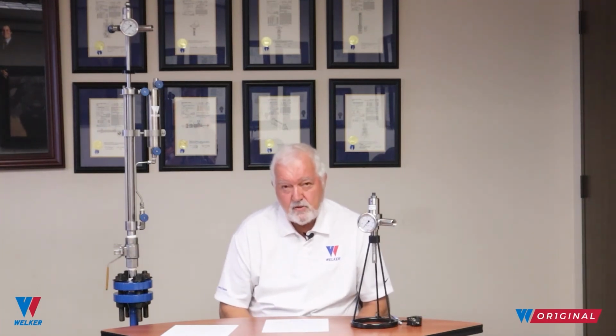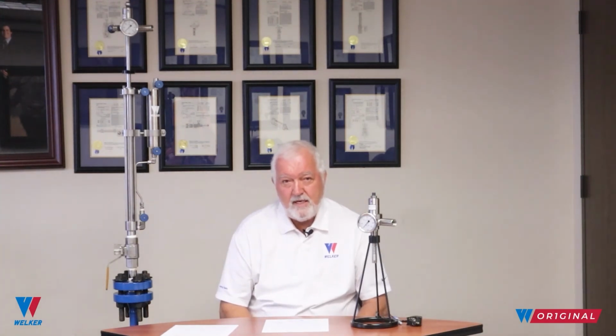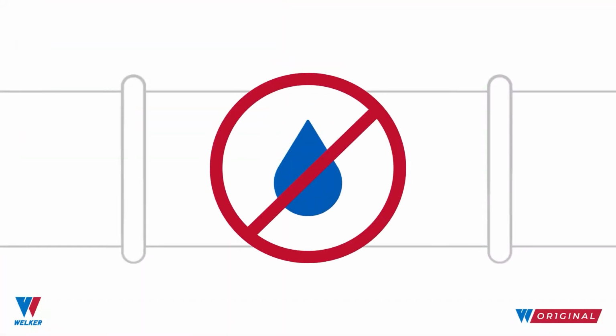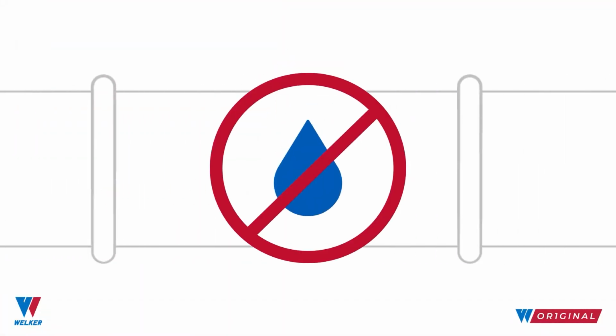The original IRD and IRA were designed not to create liquids where liquids did not exist. The measurement world of the 1970s and 1980s did not see or allow rich hydrocarbon streams in transmission lines where this device was installed. Pipelines had gas processing plants that stripped the liquids out, guaranteeing clean and dry natural gas flowing through the line. The IRA and IRD were the answers to the gas industry at that time—they took clean, dry natural gas from the pipeline and presented clean, dry natural gas to the analyzer.